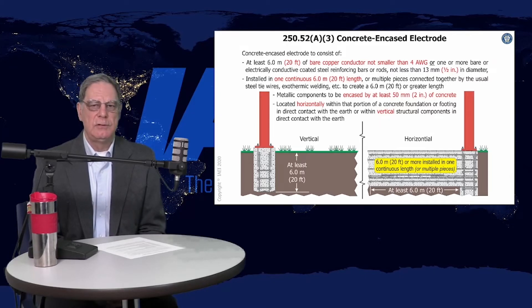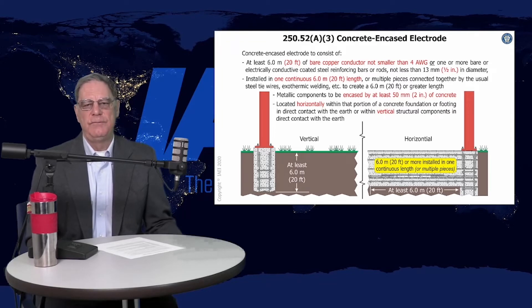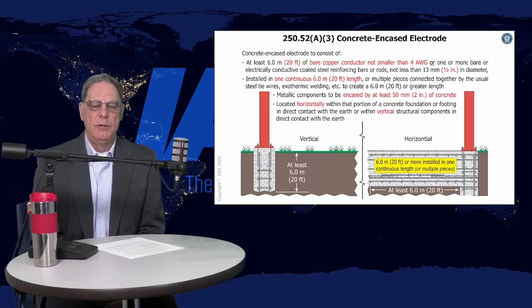One of the things about a concrete encasement electrode is that it's really the volume and surface area of that concrete and the volume of earth that makes the electrode. The rebar and the wire inside is part of that system that lets you connect the conductive concrete that typically has moisture around it to your electrical system.